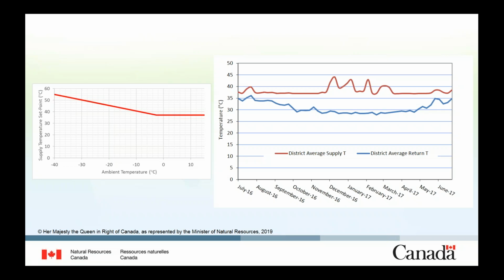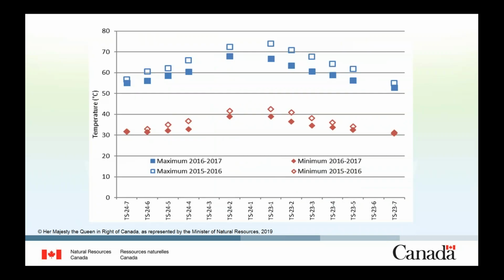And talking about the borehole thermal energy storage, those are the temperatures for the borehole. There's a couple of years there where you can see that usually it gets heated all the way to a little bit over 70 degrees, and then we extract that energy in the winter, and the borehole will go down to around 40. So it would be possible to have a combination with a heat pump. It wasn't part of the original design, so if we were using a heat pump, that temperature would come down even lower, right? But that was not the case in terms of the design. We have about 30 degrees delta T in terms of effective storage.